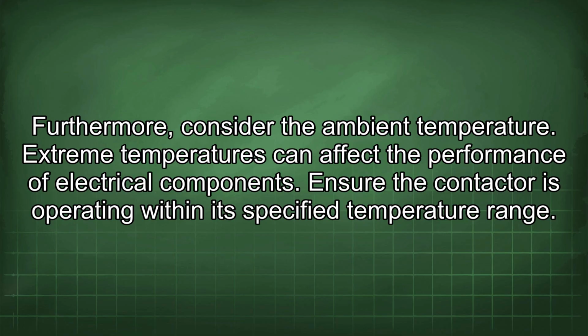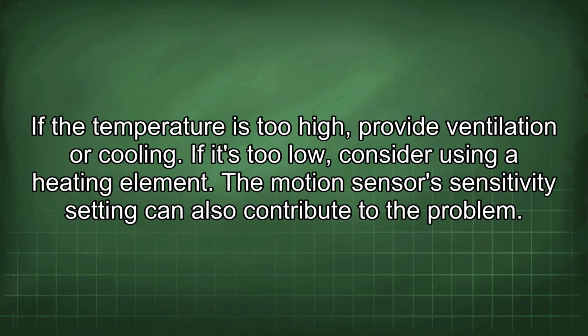Furthermore, consider the ambient temperature. Extreme temperatures can affect the performance of electrical components. Ensure the contactor is operating within its specified temperature range. If the temperature is too high, provide ventilation or cooling. If it's too low, consider using a heating element.